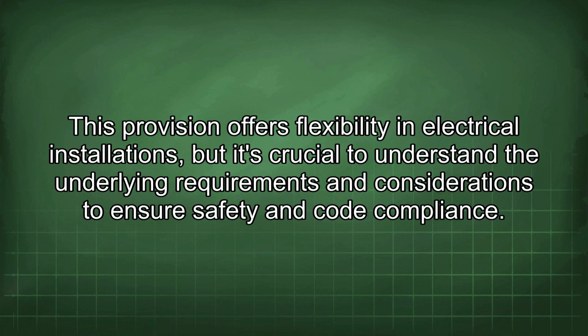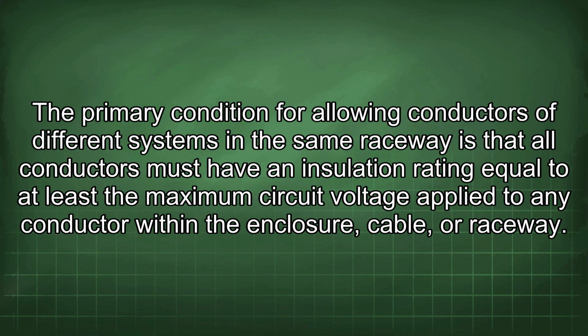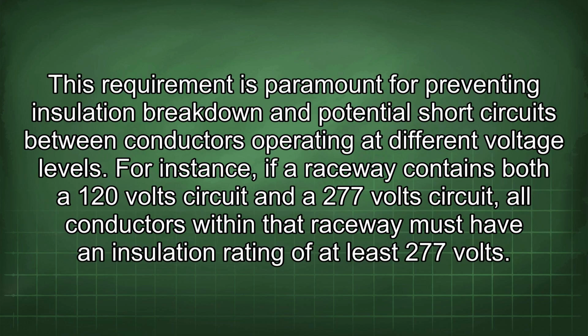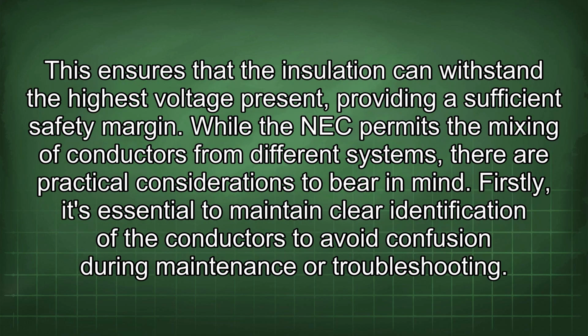and code compliance. The primary condition for allowing conductors of different systems in the same raceway is that all conductors must have an insulation rating equal to at least the maximum circuit voltage applied to any conductor within the enclosure, cable, or raceway. This requirement is paramount for preventing insulation breakdown and potential short circuits between conductors operating at different voltage levels. For instance, if a raceway contains both a 120-volt circuit and a 277-volt circuit, all conductors within that raceway must have an insulation rating of at least 277 volts. This ensures that the insulation can withstand the highest voltage present, providing a sufficient safety margin.